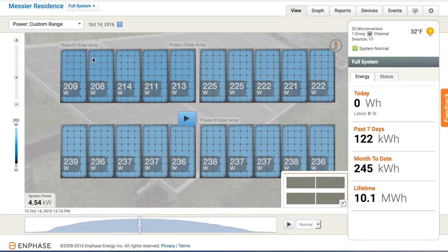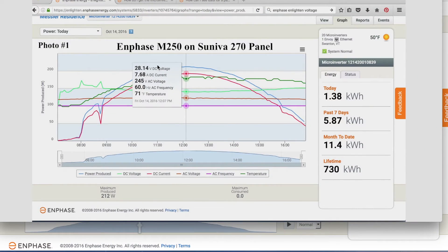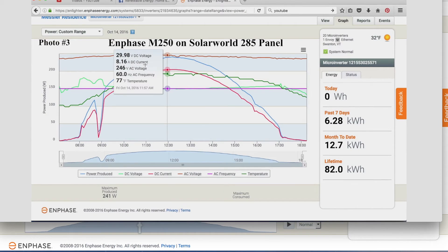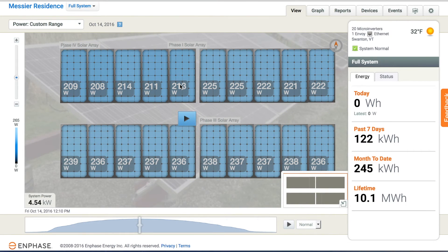Let's take a look at some specific panels and Enphase micro inverters. Enphase shows a lot of detail — we can look at both AC and DC voltage as well as current. Here we have an Enphase m250 on a Suniva 270-watt panel: 28.14 volts DC and 7.68 amps DC current. An m215 on a Solar World panel shows 29.14 volts DC and 7.86 amps — actually producing more power than the Suniva panel. And an m250 on one of the new Solar World 285-watt panels shows 29.98 volts DC and 8.16 amps DC, which makes sense as that panel can put out more power.